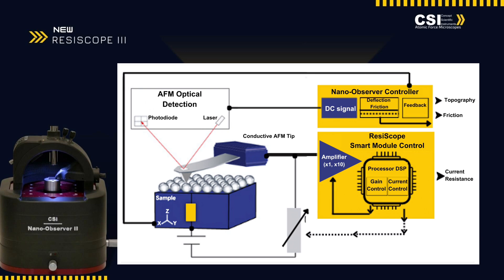Unlike standard conductive AFM, the ResiScope offers enhanced functionality through its unique gain selection system and current limiter. These advancements prevent damage to both the tip and the sample during sensitive measurements, providing a distinct advantage in detailed analysis.